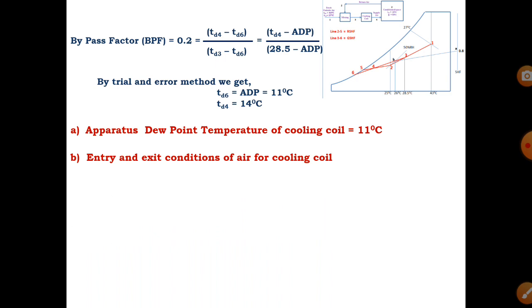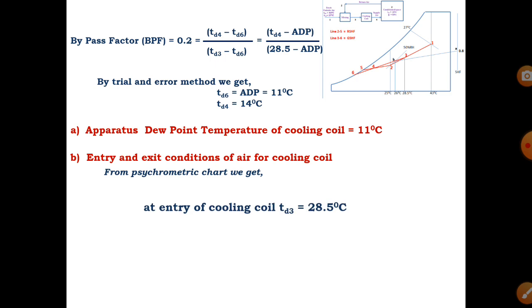Once all values are obtained, the psychrometric part is essentially complete. First answer: Apparatus dew point temperature = 11°C, obtained from trial and error. Second answer: Entry condition of air to cooling coil — TD3 = 28.5°C, TW3 = 20°C (wet bulb). Exit condition from cooling coil — TD4 = 14°C, TW4 = 13°C (wet bulb). These are the entry and exit conditions for air at the cooling coil.